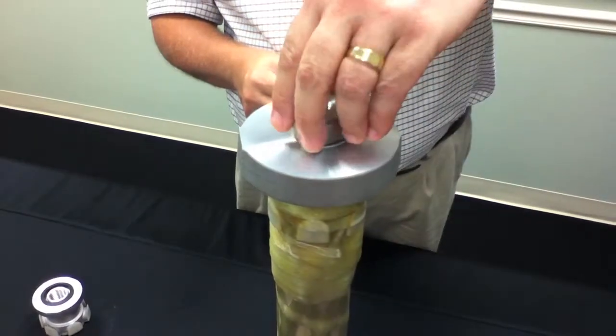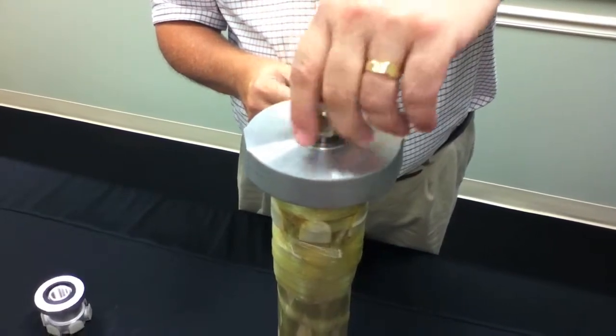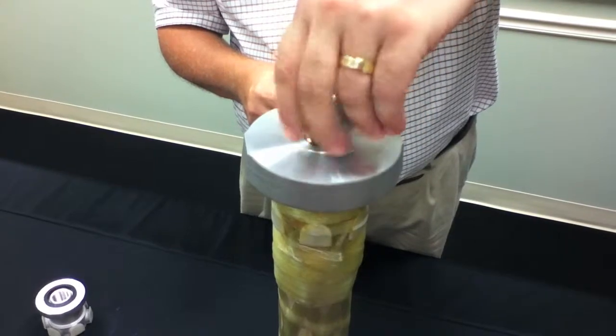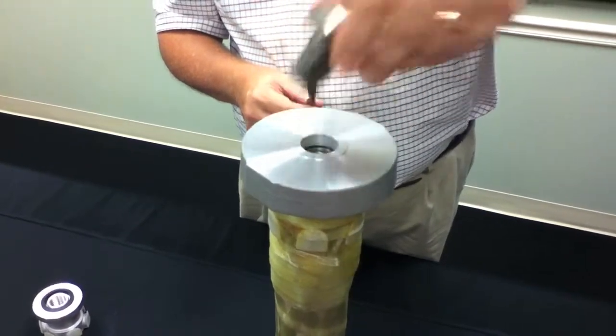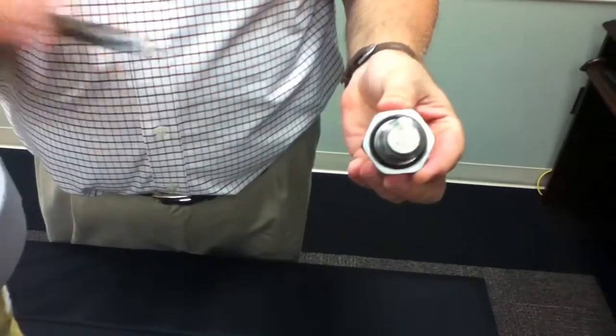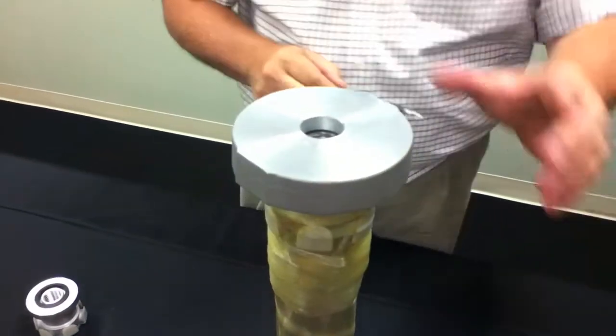The first thing we have done is, under the top bolt where the NEMA four-hole pad will be attached, we have a sealing gasket on the underside of this bolt that will seal against the top end terminal.